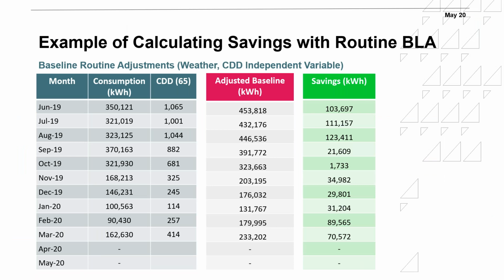Here you can see the savings that we're having. Looks good in June, July, very good savings. September, something happened, 21,000. What could be the reason? Maybe we're using water-cooled chillers, and the wet bulb is high during that particular month. Maybe we're using wet walls on air-cooled chillers, and since it was really humid, maybe something happened with the controls. Maybe someone played with the controls, decreased the supply temperature on the chillers, and we didn't have a lot of savings. However, if you look at October, it's really very low.